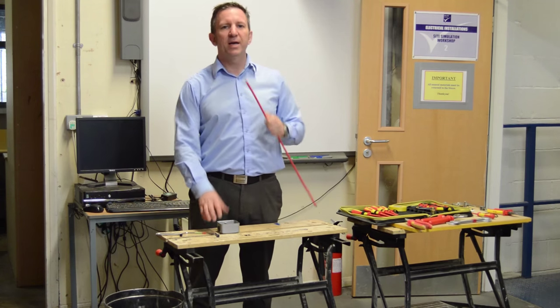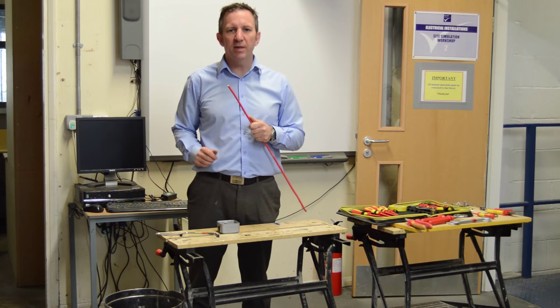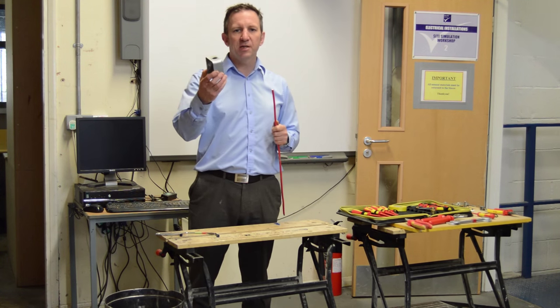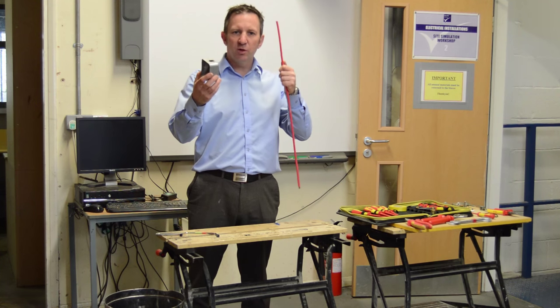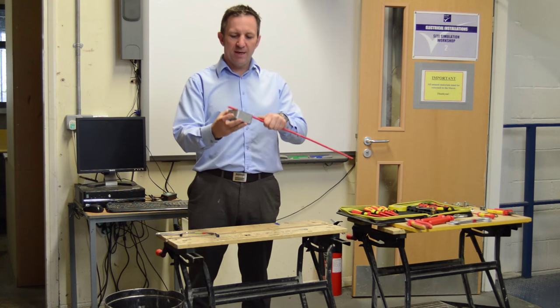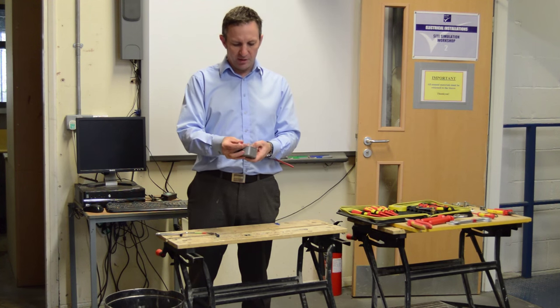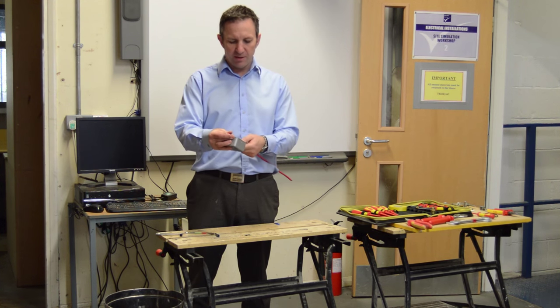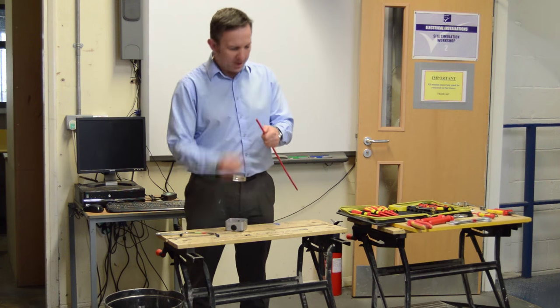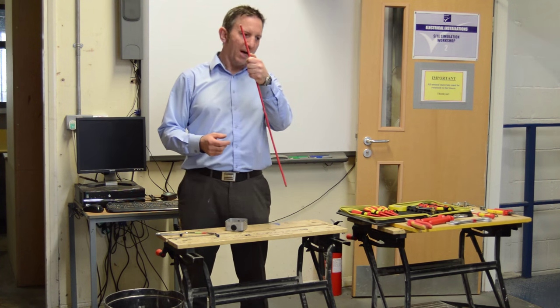OK now we're ready to decide how much of the outer sheath we need to strip off. So we get our accessory which the MI cable is going to go into. We're going to put it in and remember like always we're going to add two fingers. So when we add two fingers a little bit of a spare that is where we're going to strip off the outer sheath. Now we're going to strip off the outer sheath.